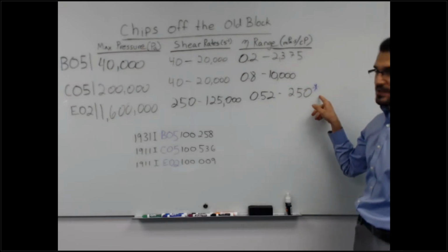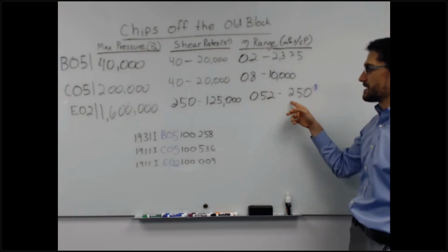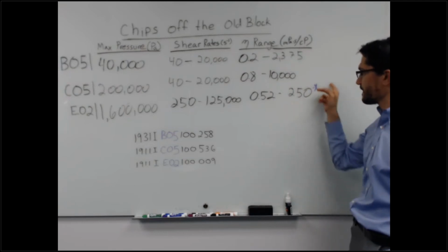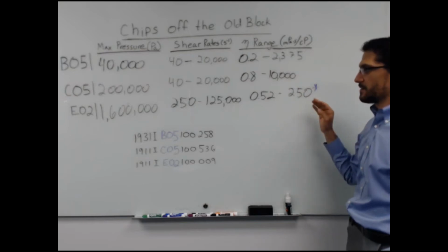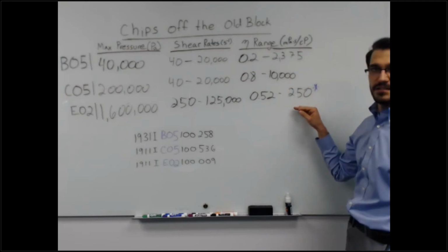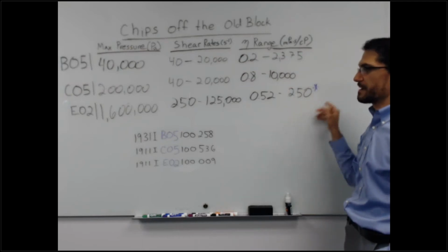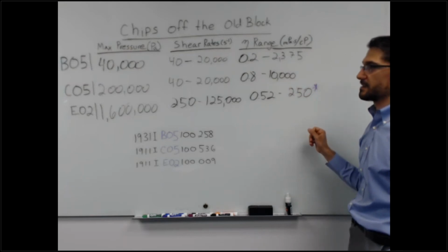This star indicates that more advanced users can potentially explore higher viscosities, but for the full capabilities of the initium instrument, 250 is the limit. We can walk through that maybe in a future video, how you could explore higher viscosity samples.